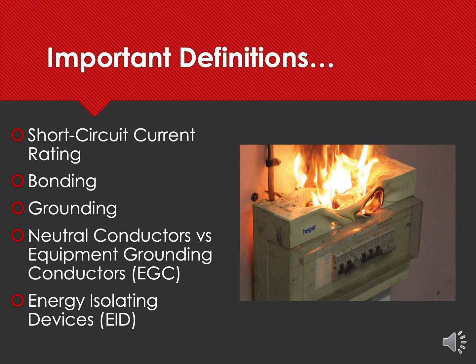Last but not least, a lockout-tagout term is called an energy isolating device. We need to be able to differentiate EIDs from control circuitry. Under lockout-tagout, it would be illegal to lock out a control circuit. We can only lock out, tag out EIDs. And so we'll go through pictures of the various panels we're talking about here today, and I'll outline where the EIDs are and where the control circuits are. So let's go to the next slide.